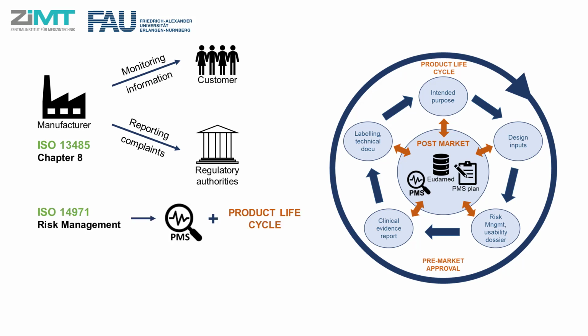ISO 14971, related to the application of risk management to medical devices, is deeply connected with the product life cycle and the post-market surveillance. In the pre-market phase, the manufacturer must ensure that the probability and the severity of all damages of the medical device are addressed, that countermeasures have been taken, and all the residual risks are acceptable. This analysis shall be iteratively done by the manufacturer in the PMS phase when new risks emerge from the market. The manufacturer shall always ensure that the risk-benefit ratio analysis is benefit-orientated.